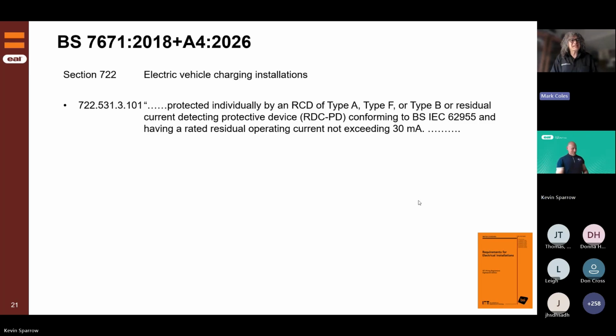Yes, sorry. So this is section 722, electric vehicle charging installations. Now, what's gone in here is, right in the middle of all of that, you'll see in brackets RDC-PD. So an RDC-PD is a residual current device for DC, which are coming through. They haven't really existed up until now. But RDC-PD, PD stands for protective device. And there are other RDC-DDs, which are disconnecting device.